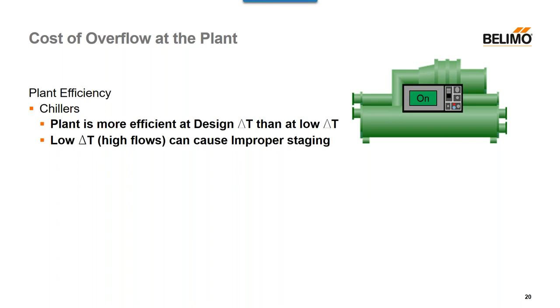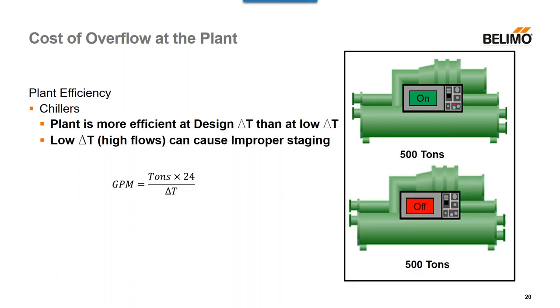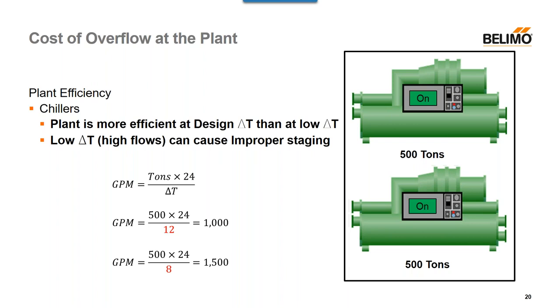This also affects the plant. The plants are going to be responding to what's happening at the coils, so we want to address it at the coil first. The plant is more efficient at design than at low Delta T. Low Delta T causes increased flow and a higher hydronic requirement that could include additional chillers coming on. For example, with two 500-ton chillers, at the design Delta T of 12 degrees we need 1,000 GPM to maintain the loop. But if Delta T depresses from 12 degrees to 8 degrees, we now exceed that GPM requirement and have to bring on another chiller — meaning additional cooling fans, cooling towers, and more energy used unnecessarily, when we could have served that load with one chiller.